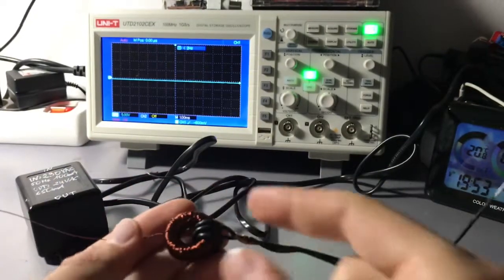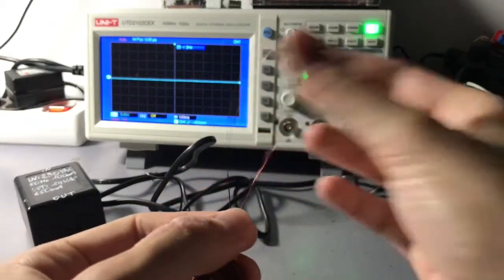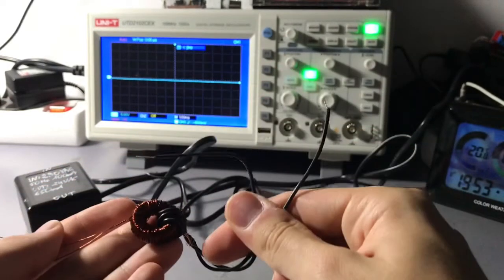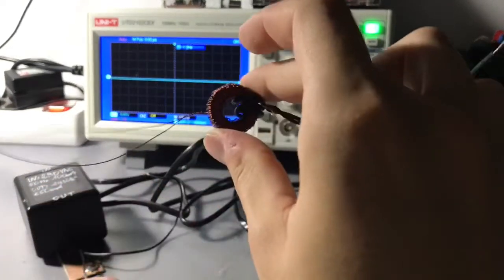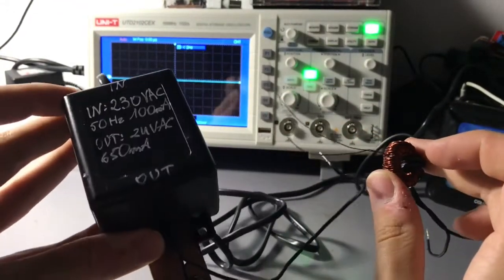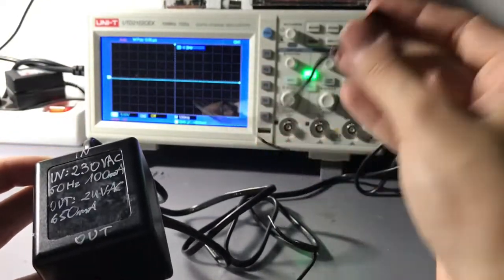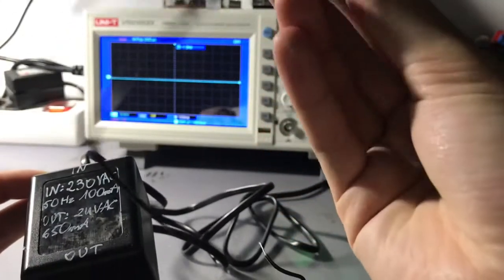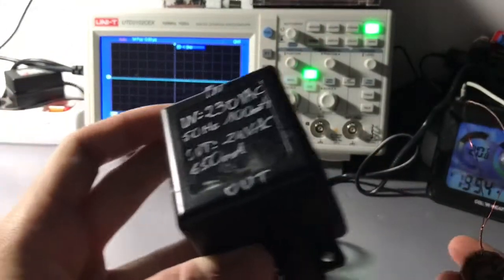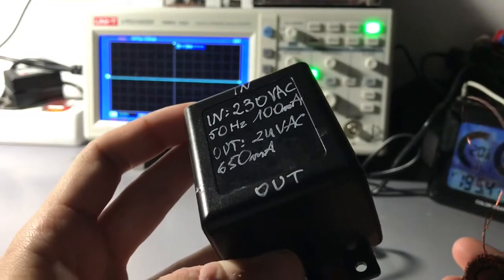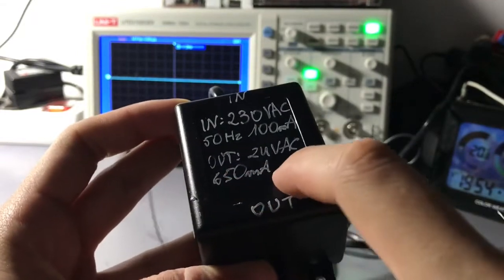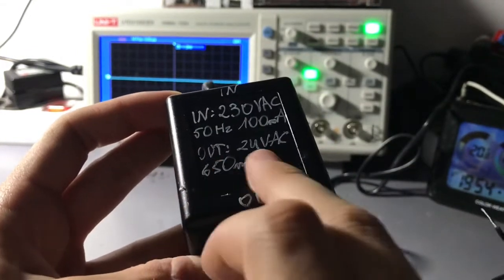So the output voltage of the transformer is proportional to the current that flows through the input. This is the transformer we'll use today to measure a short-circuit current of another transformer, and we will compare the result of a shunt resistor and a current sensing transformer like this one. Those are the parameters of the transformer we'll be using today. It truly doesn't output only 650 milliamps. Maybe that's its nominal rating, but it can output much more, and we'll see.